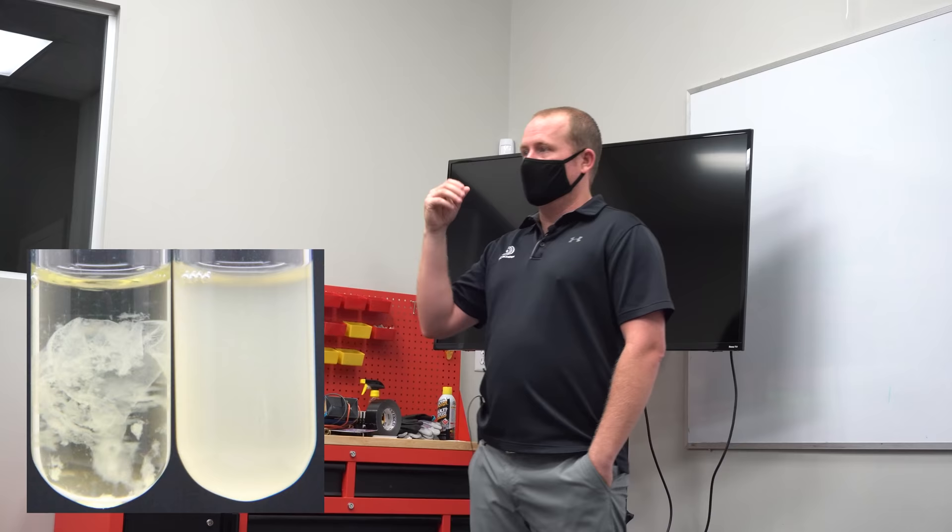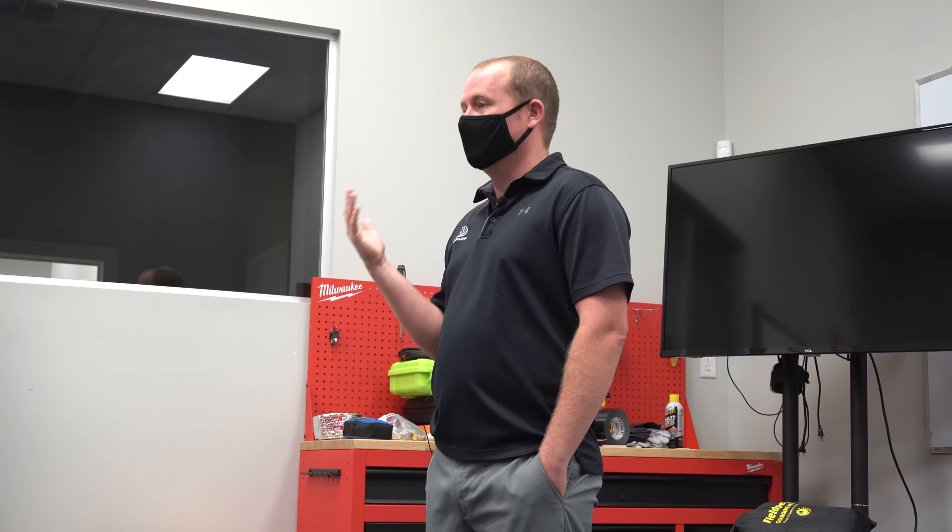So to start with, why do drains back up? They back up because it's completely untreated water. Water in the presence of other nutrients for microorganisms — lots of stuff grows. We get fungus, algae, we get bacteria — that whole bacterial zoogloea thing, which is that elephant snot stuff. All of this grows in drain pans and drain lines, and it is definitely a problem in our market.